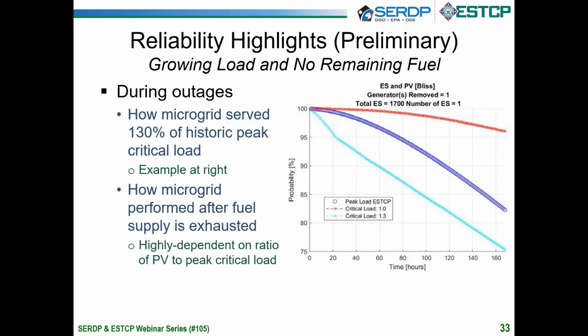For example, at Holloman Air Force Base with 5 megawatts of PV relative to 6 megawatts of peak critical load, if you take 10% of that load, you have an 8-to-1 peak PV to peak load ratio. Adding a multi-megawatt battery in that setting offers quite a bit of resiliency even without any fuel supply. On the other hand, if you don't have high ratios of PV and battery to peak loads, the coverage of even 10% or 30% of loads at any level of reliability only lasts a handful of hours at best.